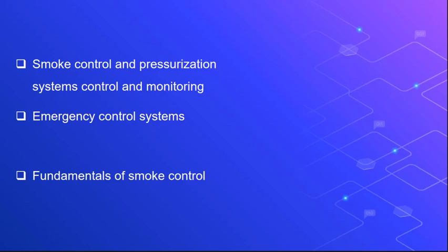The emergency control system that will automatically perform the necessary control functions in case of fire should have the following features and functions. Releasing the electromagnetic door holders and similar devices that keep open the fire doors and other openings that need to be closed during a fire. Activation of stairwell and elevator shaft pressurization devices.